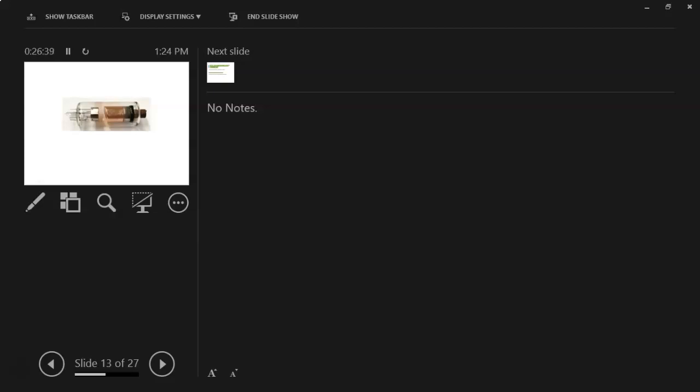And this is all lead lined. It's lead lined glass, which means that the X-ray photons cannot get out of this glass tube except for one little tiny window that is unleaded, so that the X-ray photons can come out. So this whole thing is lead lined, except for just a little window. And I don't know where the window is, but somewhere, maybe down here or something. The glass is leaded, so that the X-rays just get absorbed in the lead. They can't come out. So they leave one little part of that glass unleaded so that the X-rays can come out.